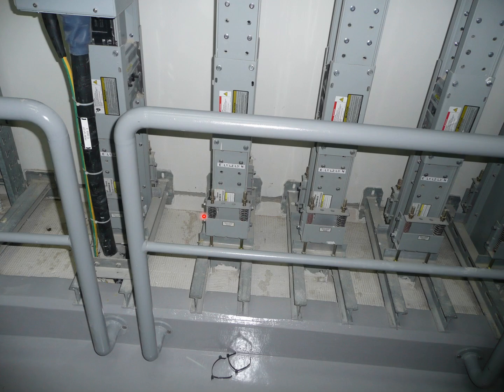Friends, this shows the electrical rising vertical plan. In reality we provide a minimum of 3 bus bars: one bus bar for UPS load, another bus bar for emergency essential load, which is then thrown onto the electrical generator, and the third may be the normal bus bar being fed through the transformer. In all normal cases, the transformer is feeding all these three loads.